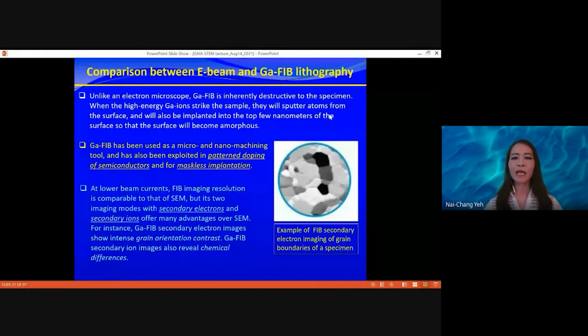If you compare focused ion beam and electron beam, they have similarities and differences, but gallium ion beam is usually inherently destructive to the specimen. If you use high energy, you can remove a lot of material, or you can implant ions into the sample by a few nanometers. So it's very different.